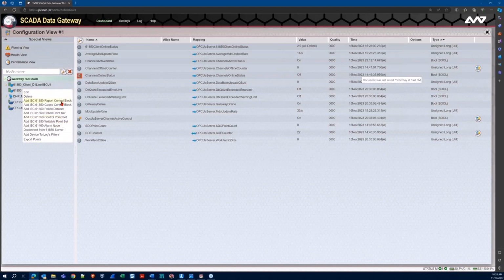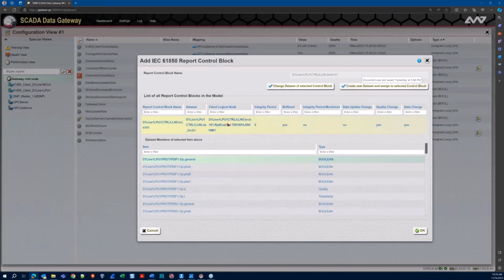But if I've done my top-down engineering process, I've already created reports on my device, or maybe they just came pre-configured in my CID from the manufacturer, then I have the option to just add a 61850 report control block. In this particular case, this server only has a single report control block, but if there were multiple, each one would be listed here.